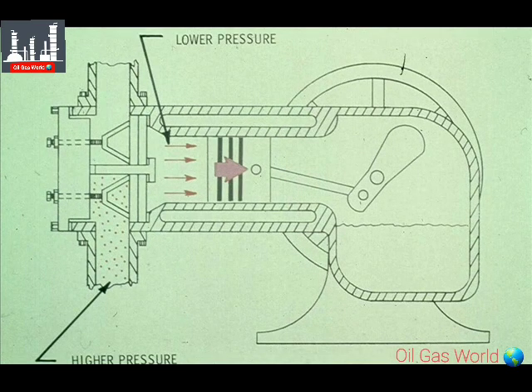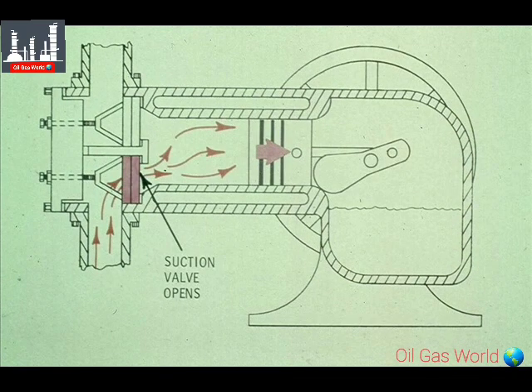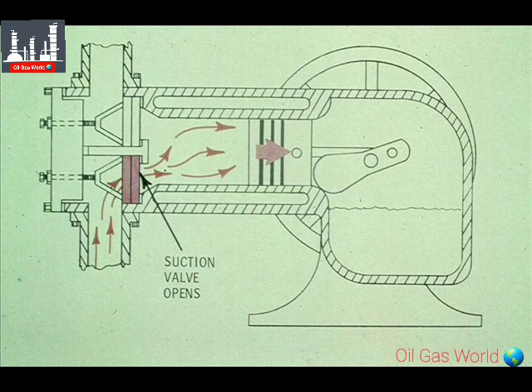Now, the atmospheric pressure outside the cylinder is higher than the pressure inside. The result is that the atmosphere forces the suction valve open, allowing air to flow into the cylinder. This continues until the piston reaches the end of the suction or intake stroke.